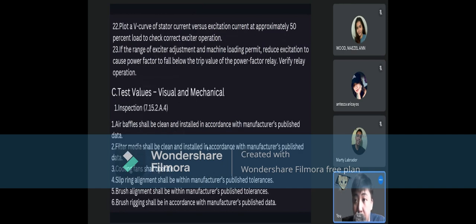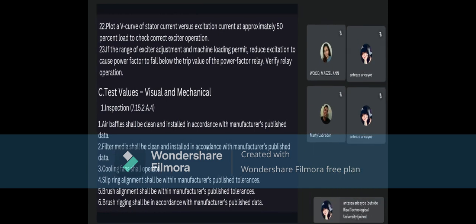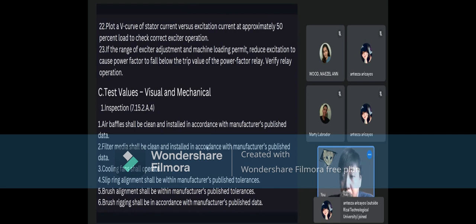Next, please. 22. Plot a V curve of stator current versus excitation current at approximately 50% load to check correct exciter operation. 23. If the range of exciter adjustment and the machine loading permit, reduce excitation to cause power factor to fall below the trip value of the power factor relay. Verify relay operation.